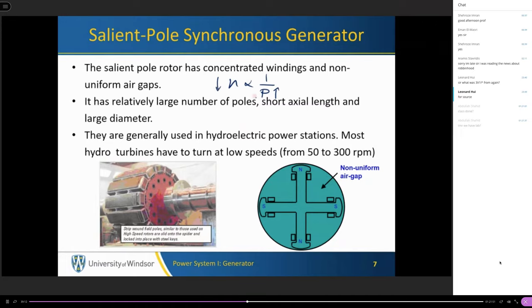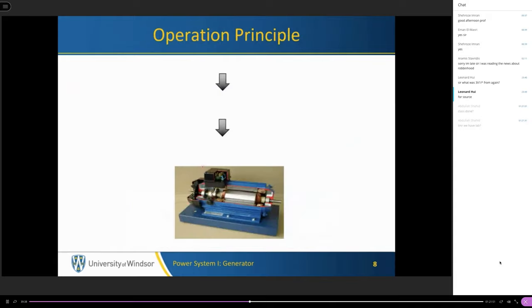And that is why this type of machine is suitable for hydroelectric power stations, because the hydro turbine does not run at high speeds compared to steam turbines or gas-based turbines. They run at low speeds, ranging from 50 to 300 RPM. So typically we use this machine with hydroelectric power stations.